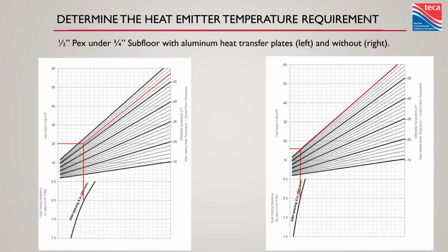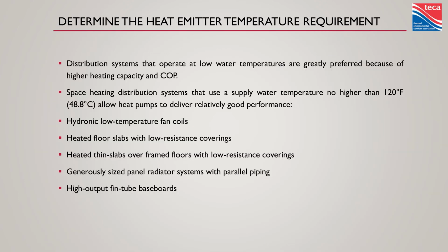Pop over to the heat transfer plates. I can drop that down to a 55 degree delta T and get 20 BTU a square foot out of it. So lowering that water temperature or increasing your heat output, however you want to look at it, these things have a great place in these kind of systems. So make sure you're sizing a system based on that water temperature. The capacity of the heat pump changes as the water temperature changes.